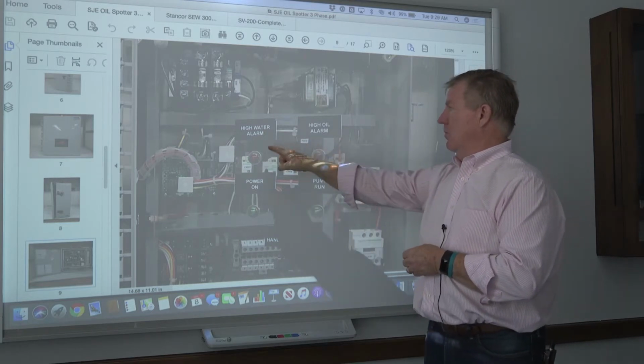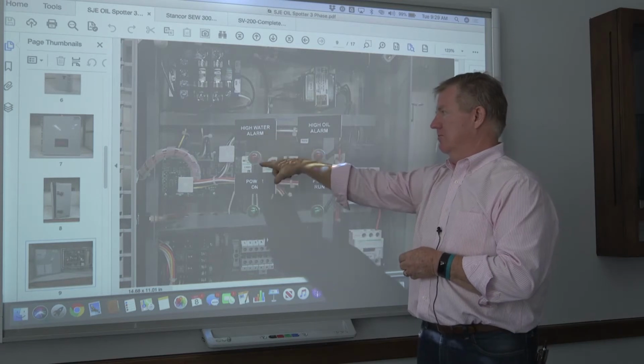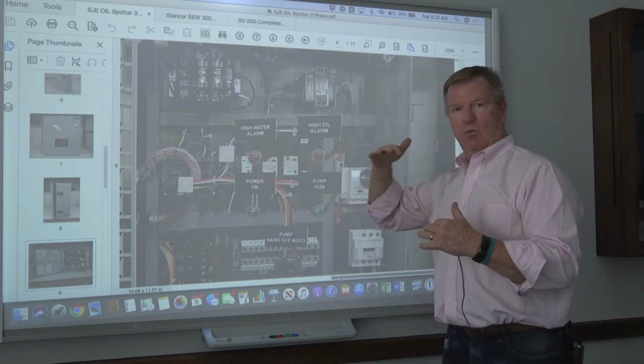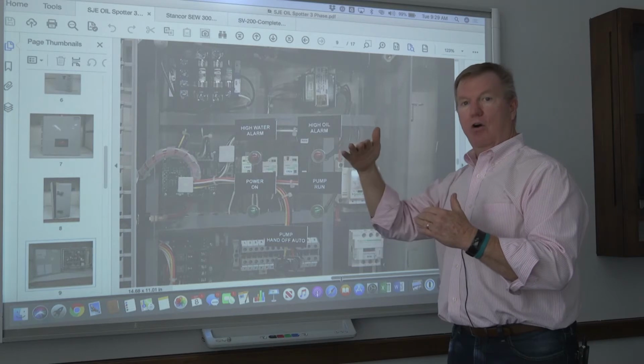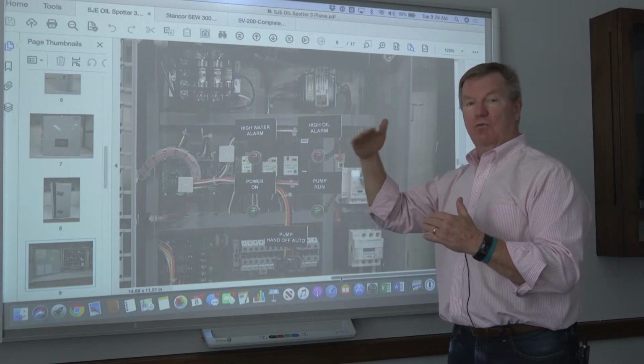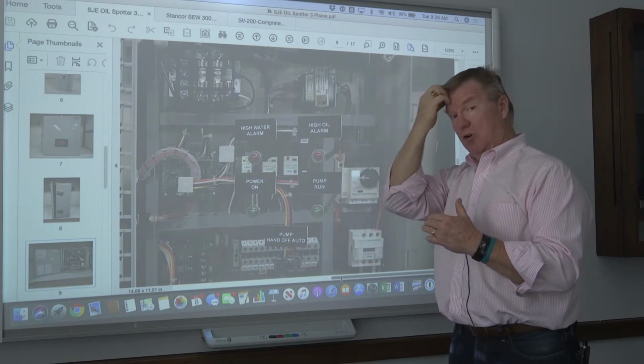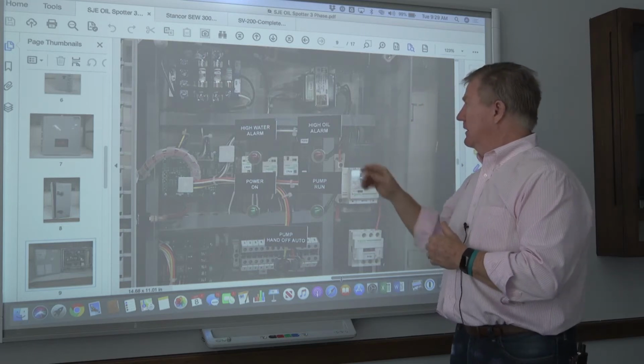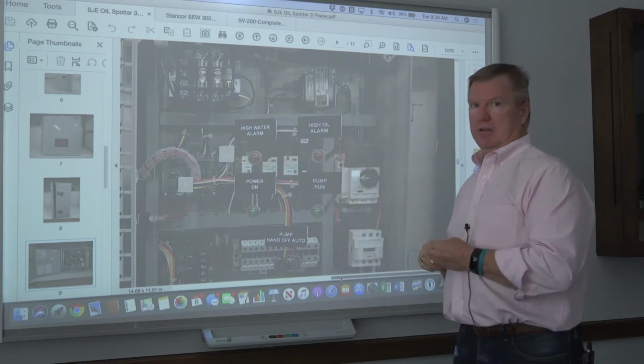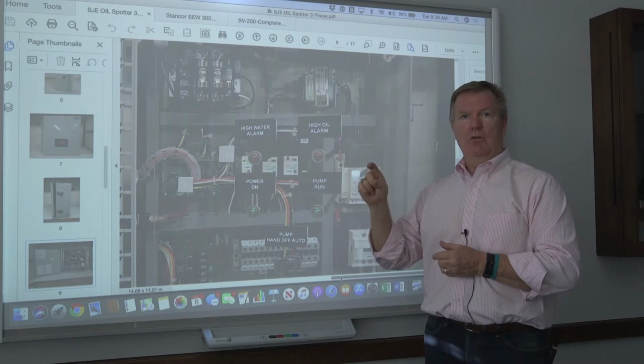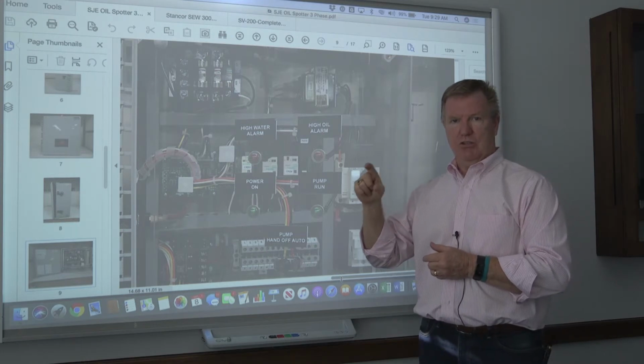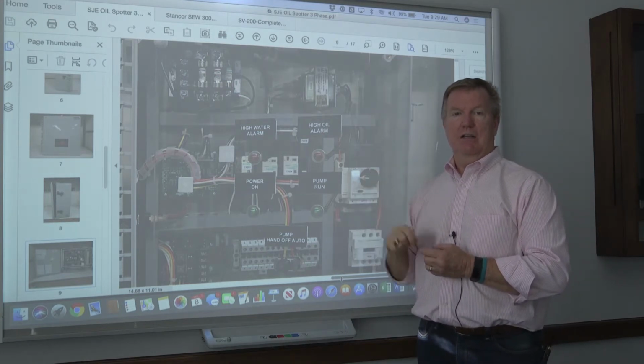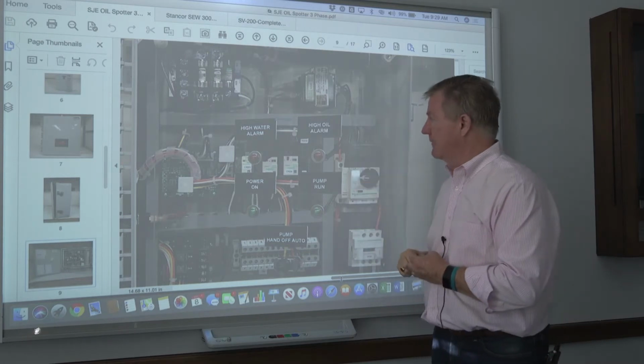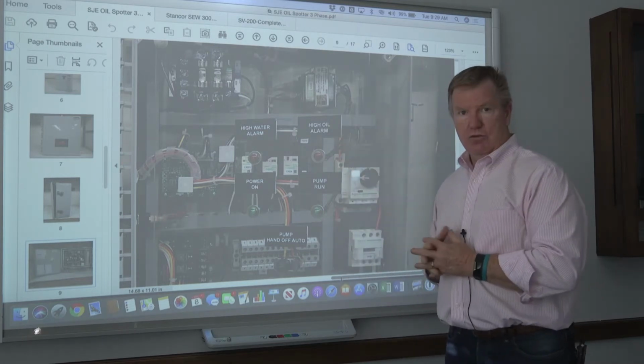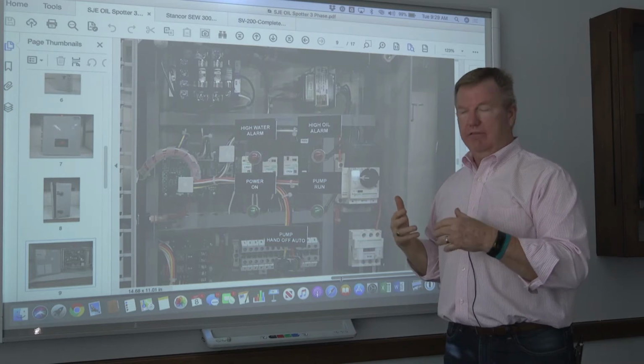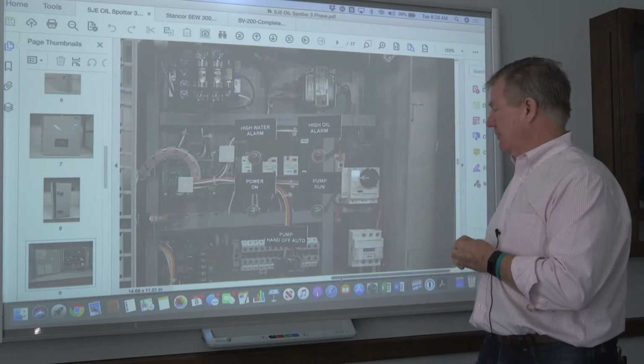Then you have two alarms. One is the high water alarm that tells you that the water has risen above the on pump level and continued to rise even though the pump was called to come on. And then there's a high oil alarm that tells you that there's a slick of oil on top of the water that has reached a certain depth that it's something you're going to need to look at. And I'm going to show you how those in particular are activated during operation.